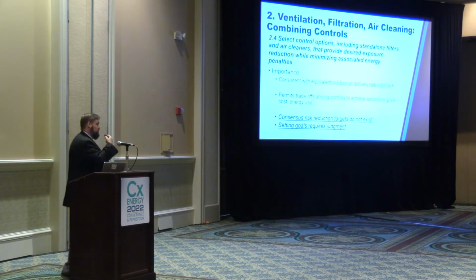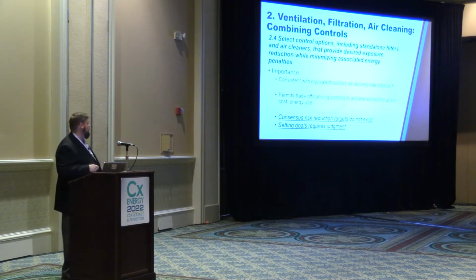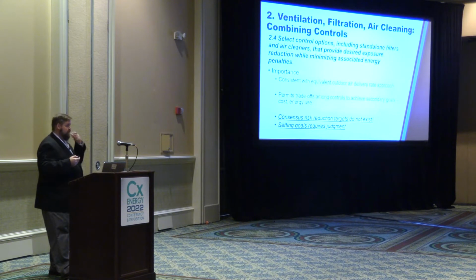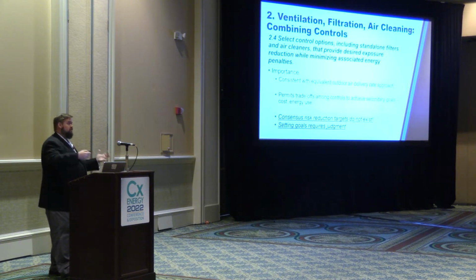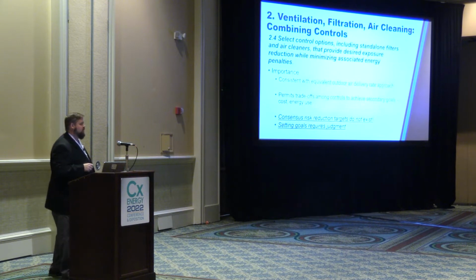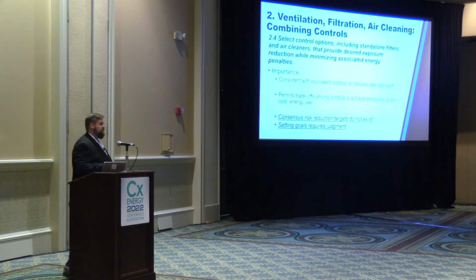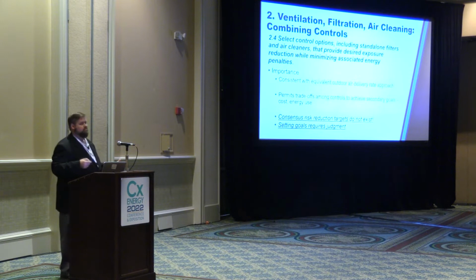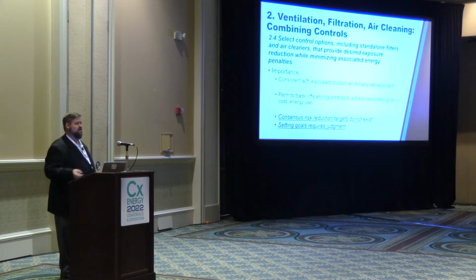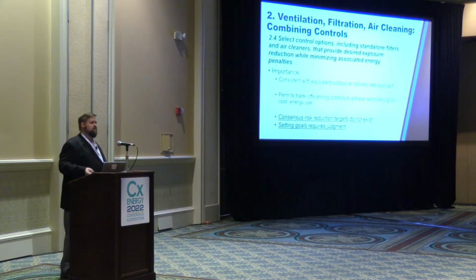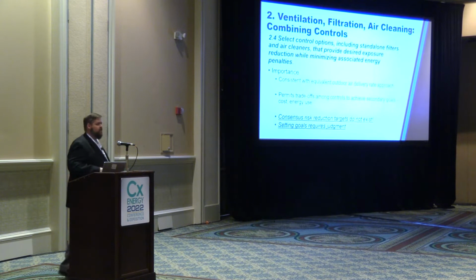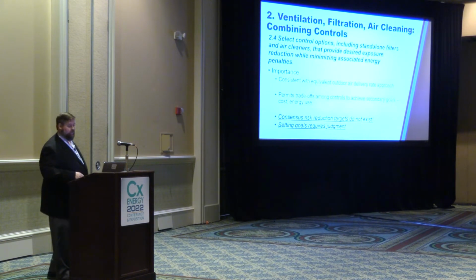There's another one where Dr. Joe Allen from Harvard and Dr. Jimenez from University of Colorado did a spreadsheet that basically said what in-room fan HEPA selection you'd need for a classroom. They targeted an ideal of 6 air changes. That's their opinion, but in talking with Joe Allen, the basis of that really is ASHRAE Standard 170, looking at different spaces and figuring, well, if it's good enough for healthcare, then this should be our ideal for other spaces in a pandemic mode.